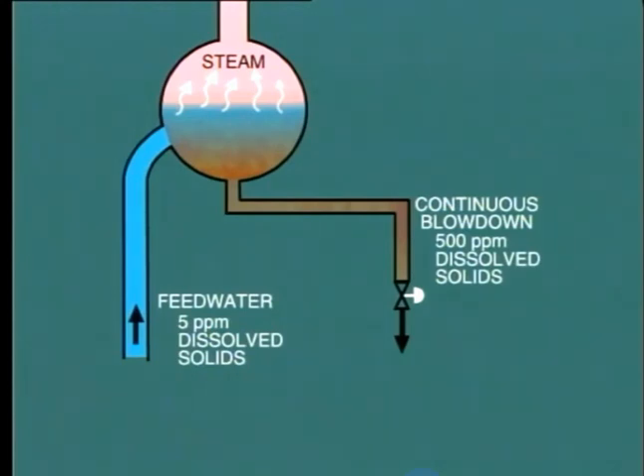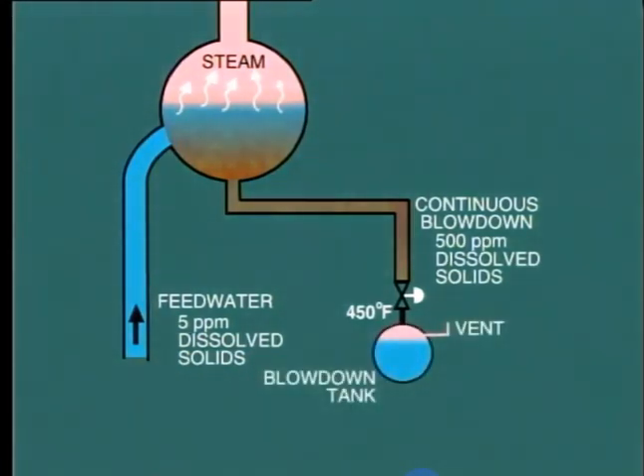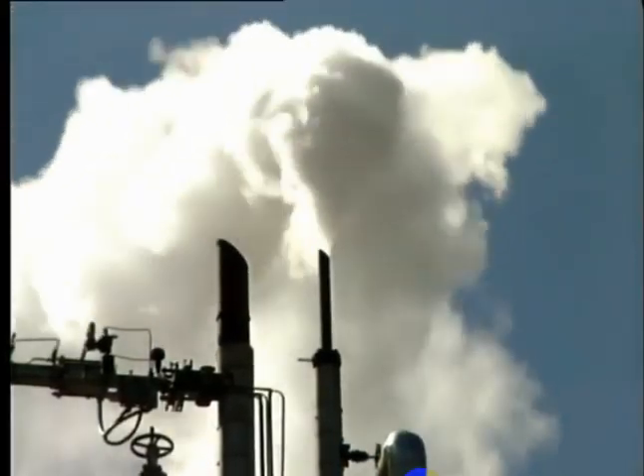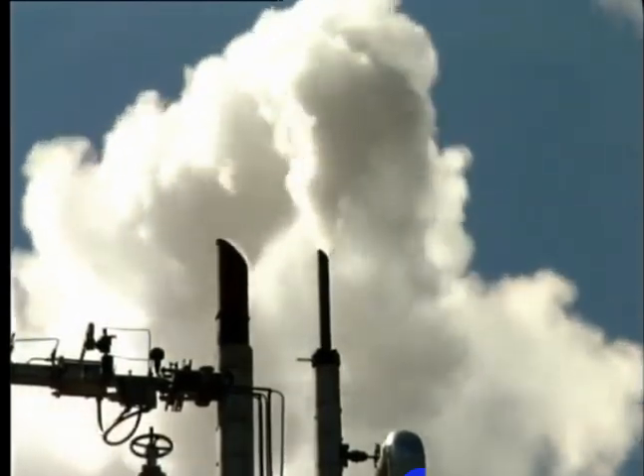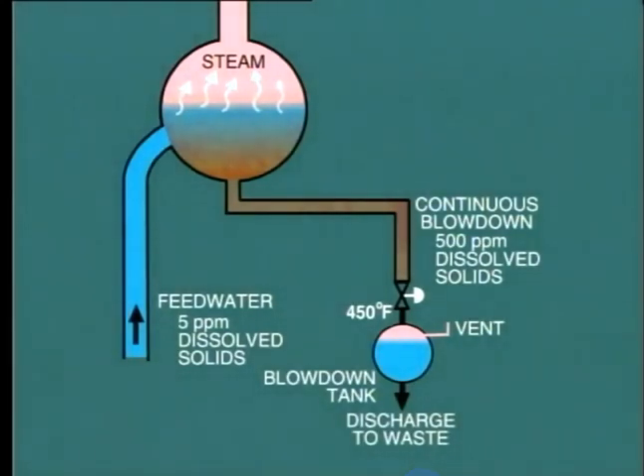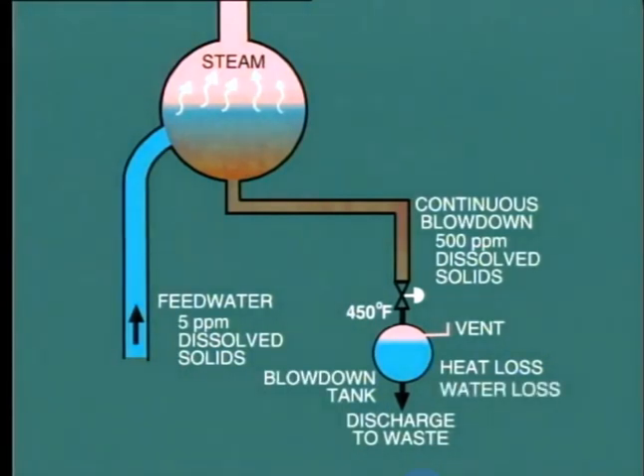As the blowdown water is at relatively high temperature — between 400 and 500 degrees Fahrenheit — it is discharged into a blowdown tank. This permits some of the high temperature water to flash off into steam and be vented to atmosphere, while the remaining water is discharged to waste. Of course, there are some losses involved: first, the loss of heat contained in the water, and secondly, the loss of water itself, with a consequent increase in makeup requirements.